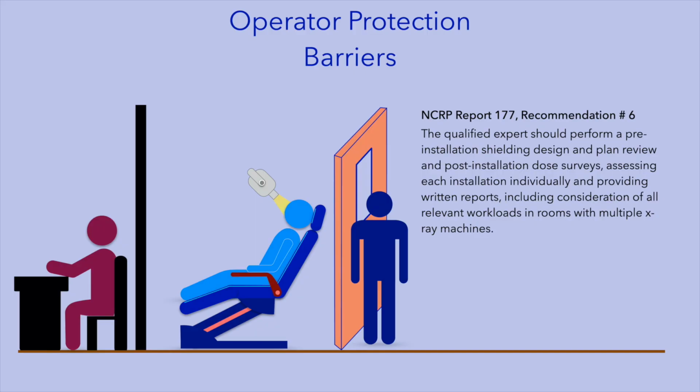Dentists should consult with a qualified expert, typically a medical physicist, who will help in the design of the radiological shielding. This shielding will consider the location of your X-ray units and also proximity of staff who may not be occupationally exposed to ionizing radiation. For example, the front desk staff.